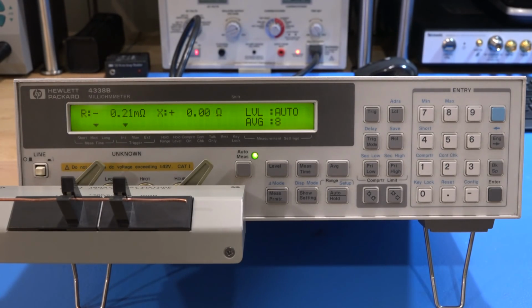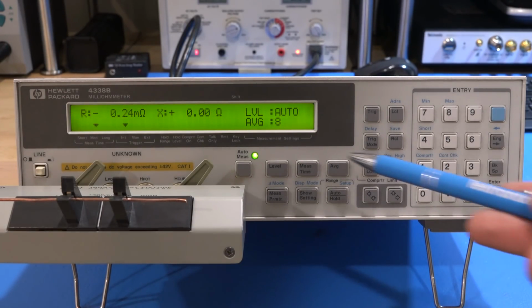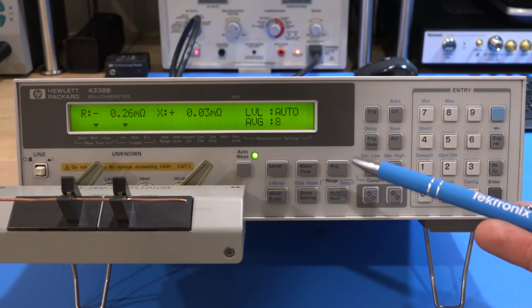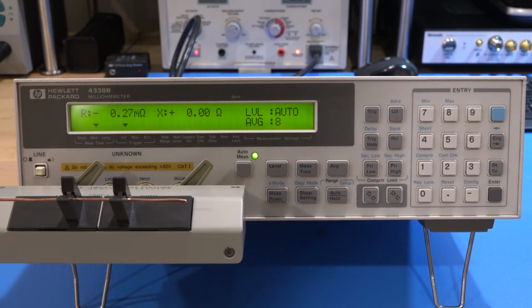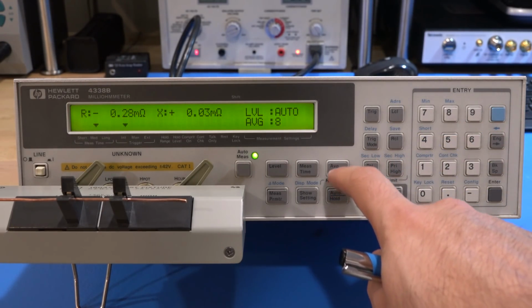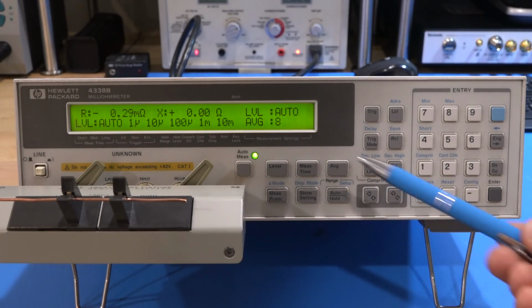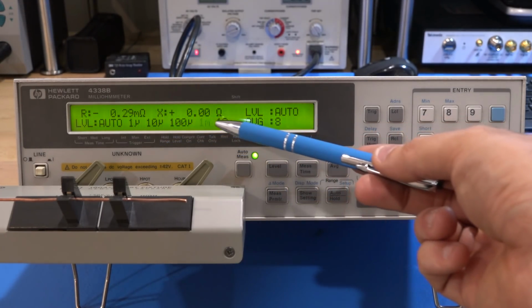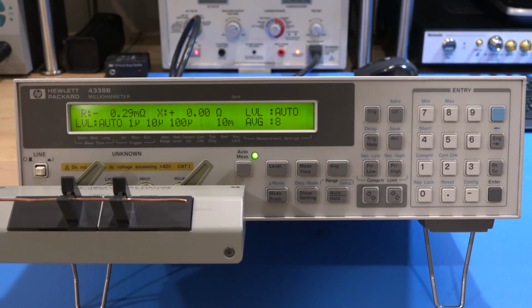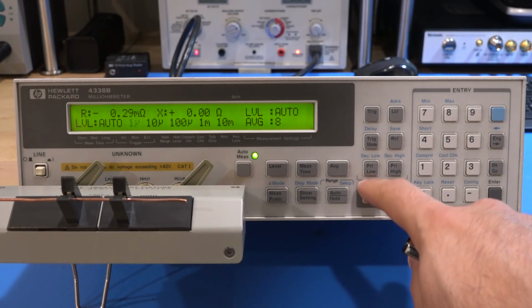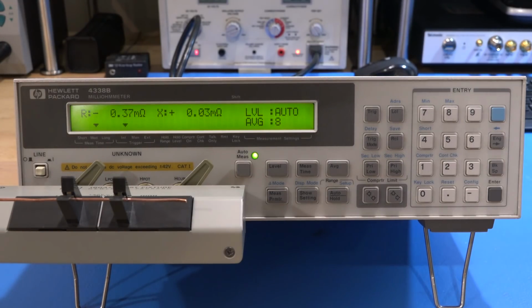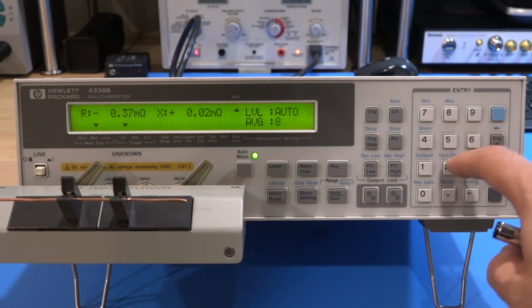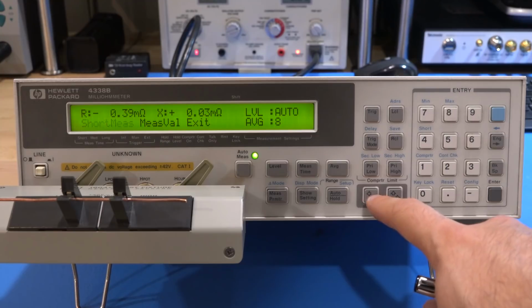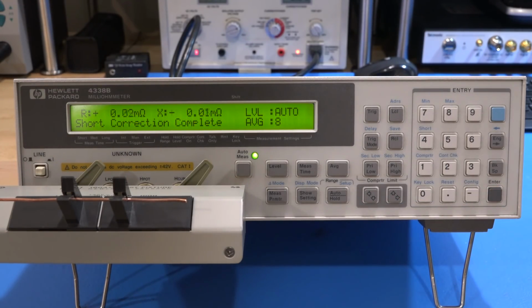So having said that, now we can remove that and try to measure a resistor that I have. Now I'm doing 8 averaging here, and I've left the level on auto, but you can choose the level to be anything between 1 micro to 10 milliamps in terms of the current that it puts through the DUT. So we're going to stick with auto here, which is fine for our purposes. Let me zero this one more time. This is really not a very good setup for making very small measurements, but there it is.